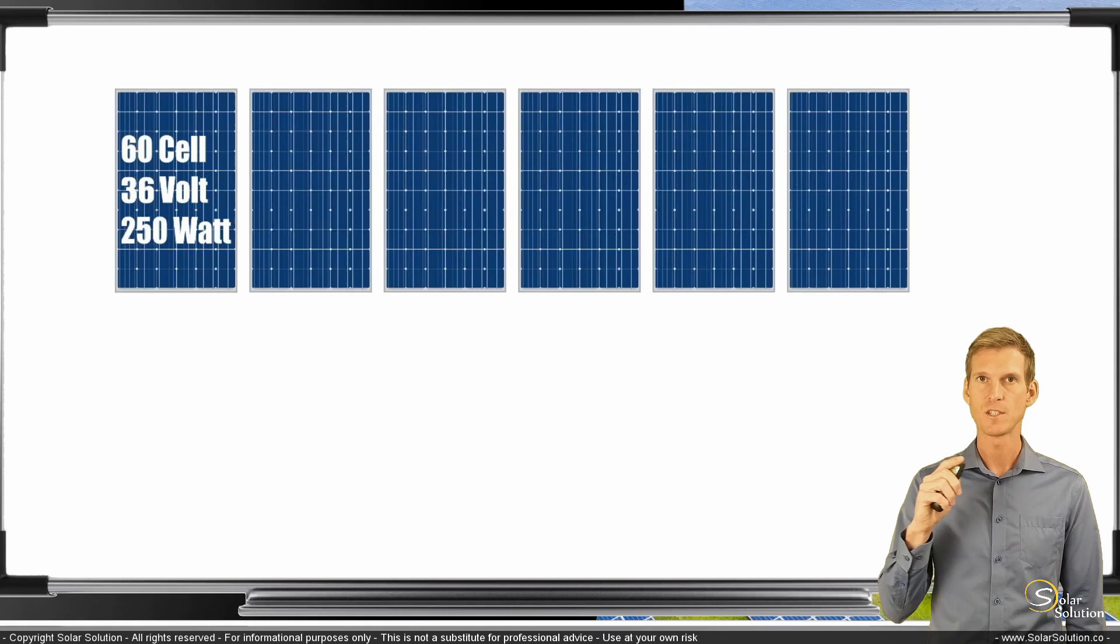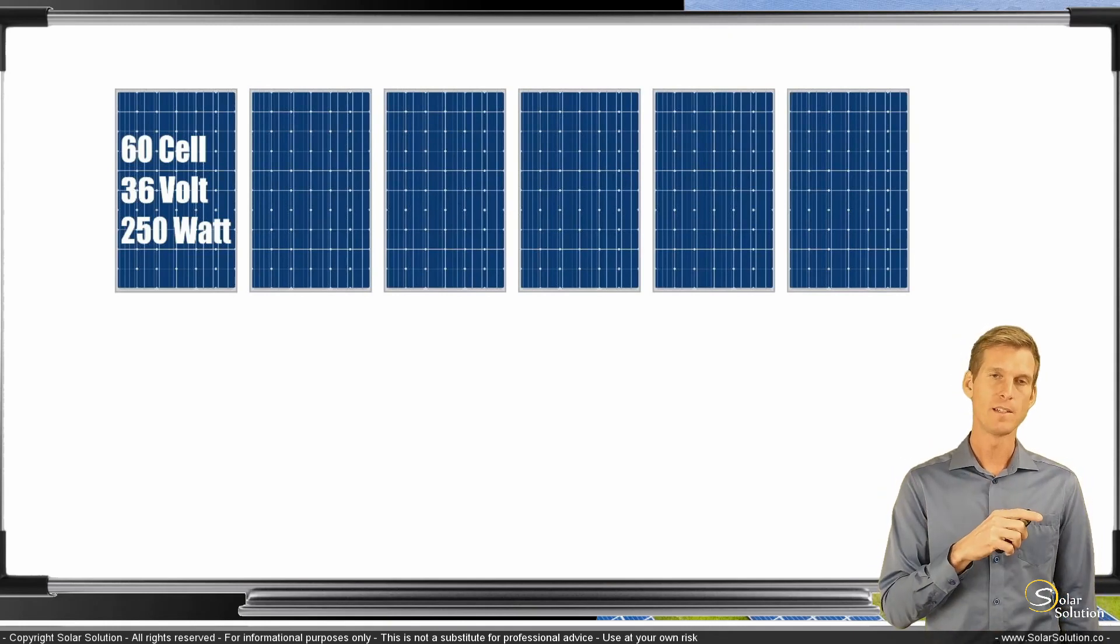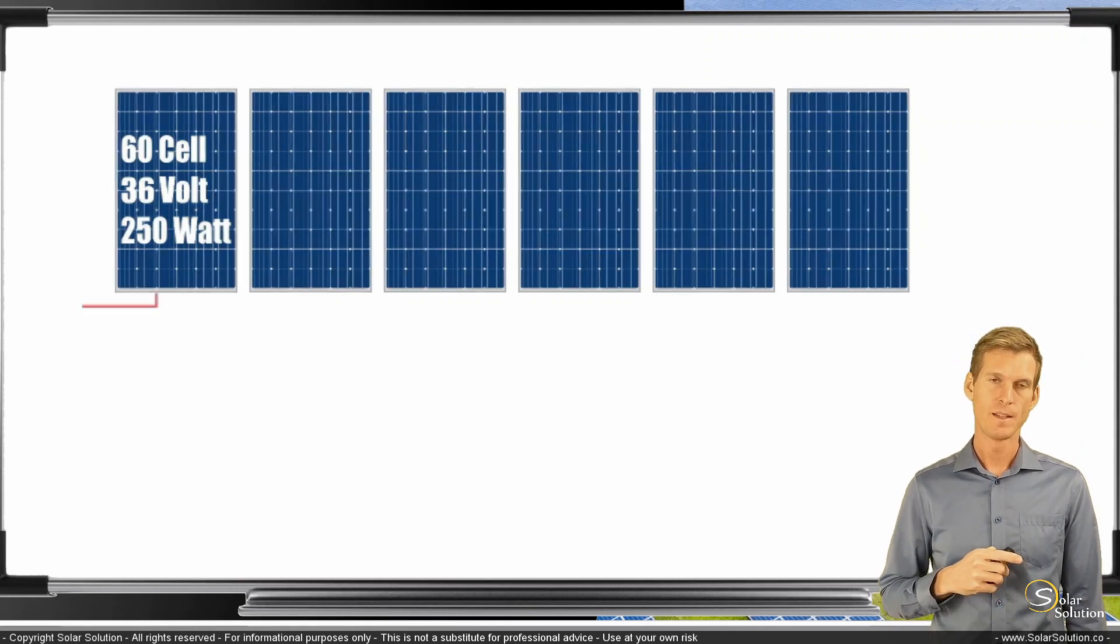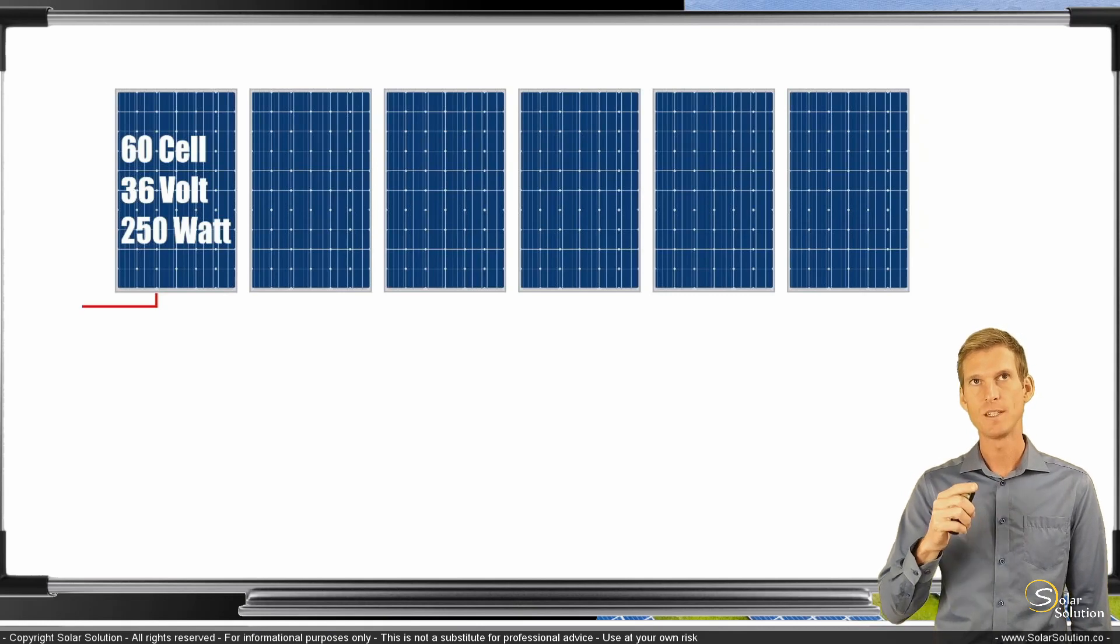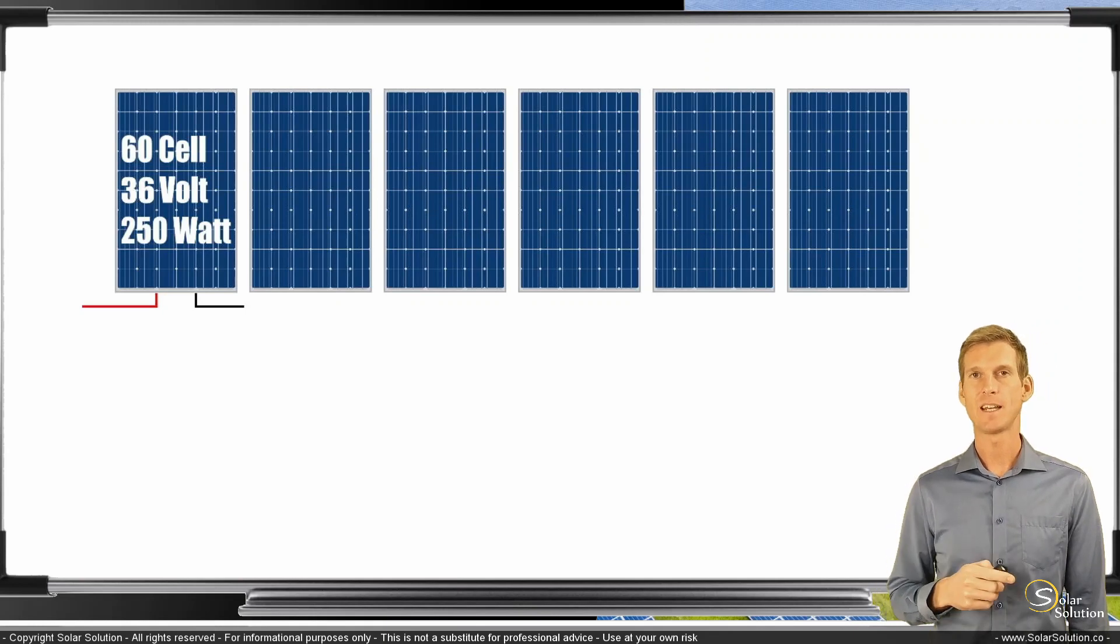We want to make one group of six panels all wired together. Now if we want to wire it together in series, we start with a positive lead from the first panel that goes into the panel and then the panel has a negative lead output, and you connect the negative output from the first panel with the positive output of the second panel.